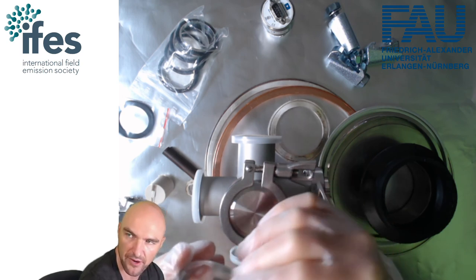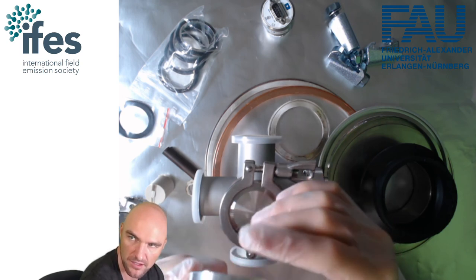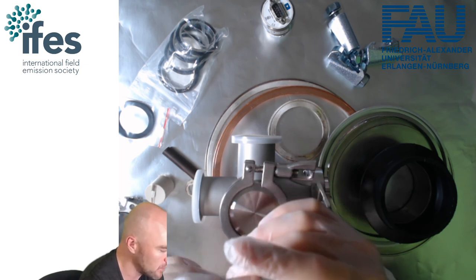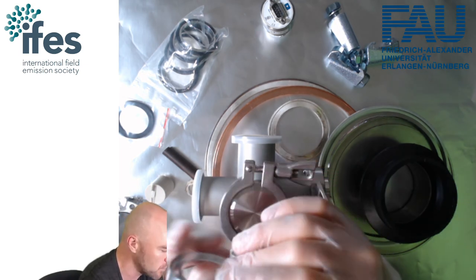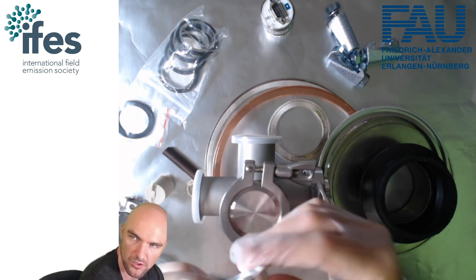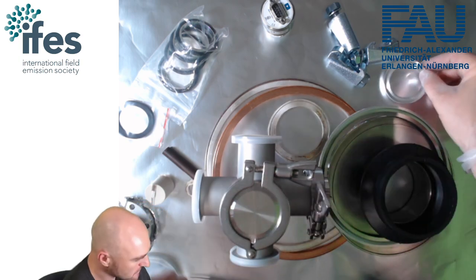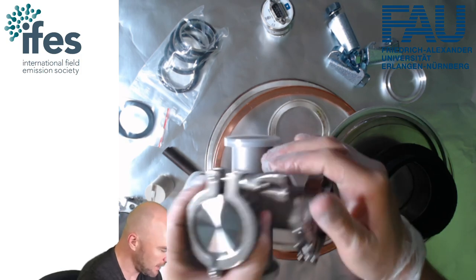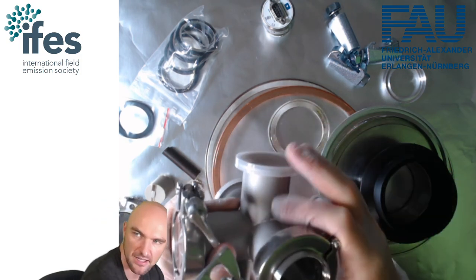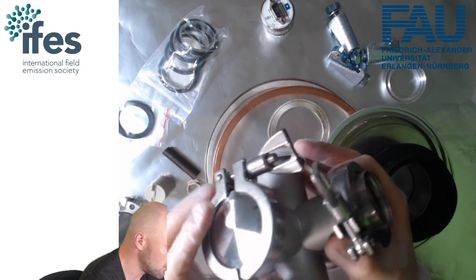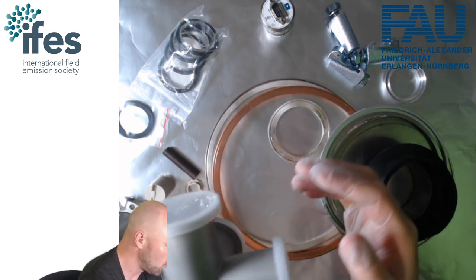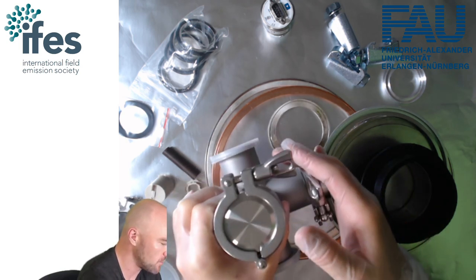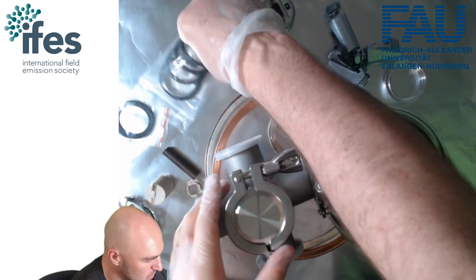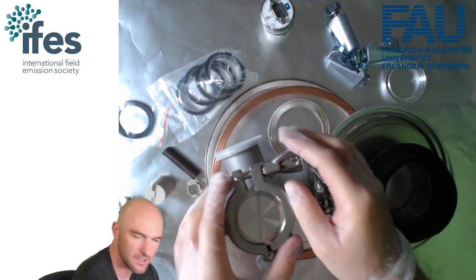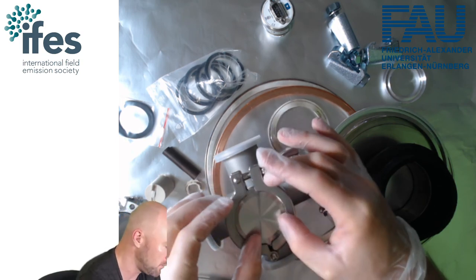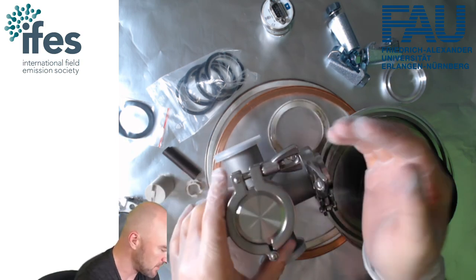And I have some friends that are building coating systems that claim they can go into the 10 to the minus 10 millibar range as well. So you can go to relatively good vacuum ranges with those as well. The KF flanges with the hand tightening only have a limitation in terms of size. You will not be able to go any larger really than 40 millimeter tube diameters. This is already what we have here. This is a KF40 flange. You can get 50 millimeter ones as well, but this is sort of the size limitation.